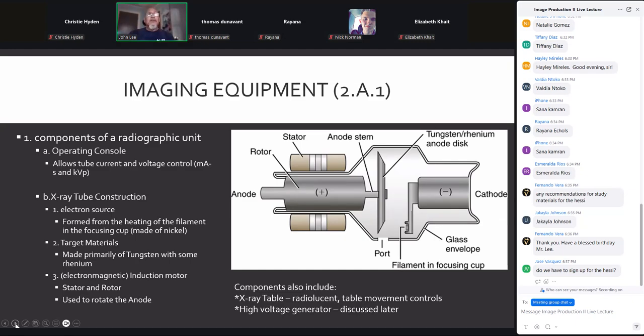Our X-ray tube. Sometimes my mouse wants to work, sometimes it doesn't. As far as our X-ray tube, be familiar with the inner workings. Remember, it is enclosed in a Pyrex glass envelope. There are some that are made of metal, but primarily we're looking at a Pyrex glass envelope for our equipment. And the reason we use Pyrex glass is, of course, to be able to withstand the tremendous amount of heat that's going to be generated during X-ray production.